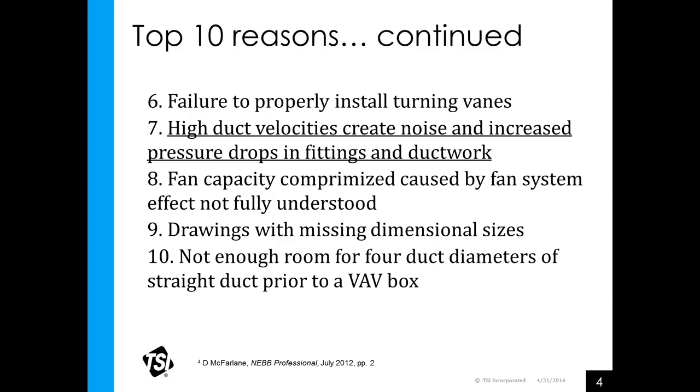Number 6, failure to properly install the turning vanes. I mean, that's fairly common. Number 7, we're talking about mostly in critical HVAC commercial applications, and these are higher velocity systems, many times approaching 2,500 FPM. And these high duct velocities, not only do they create noise, they increase the pressure drop in fittings and ductwork. So that's another hurdle that has to be overcome in a critical HVAC system.